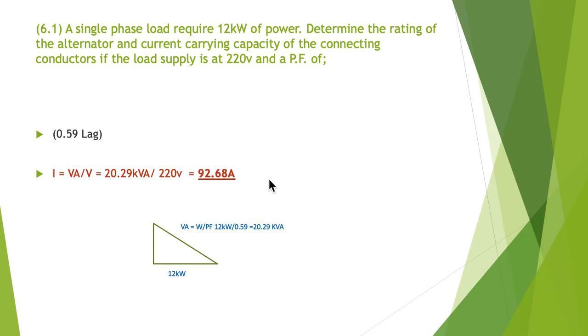And we do the whole thing again. And of course we've got to work out the VA first. So again the VA is going to be the power in watts divided by the power factor. And in this case 12 divided by 0.59 giving us 20.29 kVA. So our 20.29 divided by 220 is going to give us current of 92.68 amps. So there's our three currents.